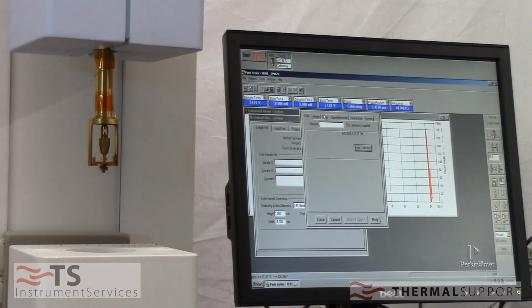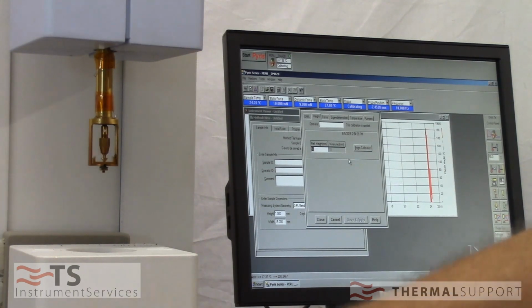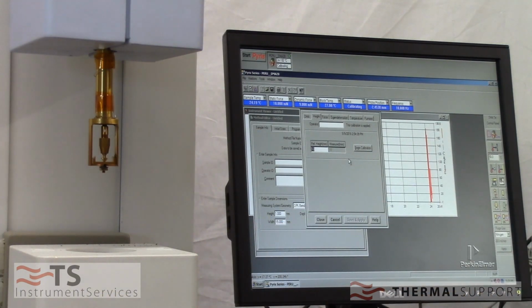Okay. DMA cal's done. We're going straight over to do the height calibration. Now, we're looking at sinusoidal force. We're looking at response, how high up it comes, how much longer it takes, amplitude, phase lag. If we're going to look at amplitude, we really need to have a high level of confidence that the instrument is reading the height that's there. So we have a slug here, a quartz slug. We've measured it 12 millimeters. I mean, not 12. I'm sorry, 10 millimeters.